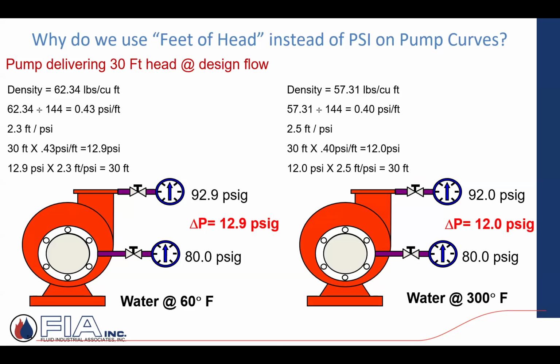So the pump manufacturer doesn't have to make different pump curves for different water temperatures. It says X number of gallons a minute, 30 feet of head. That's what I'm reading. What the gauges show is going to be different. If I'm out there with gauges trying to say, what's the pump doing, and I'm dealing with 300-degree water, I'm not going to read 12.9. I'm going to read 12 for that 30 feet of head, which is what I calculated I needed.